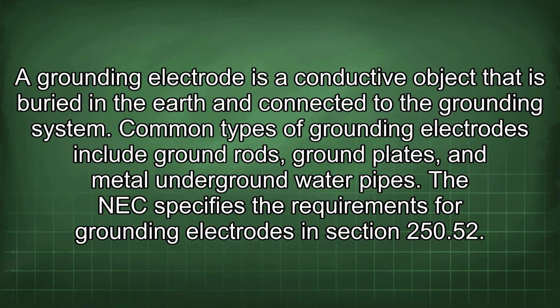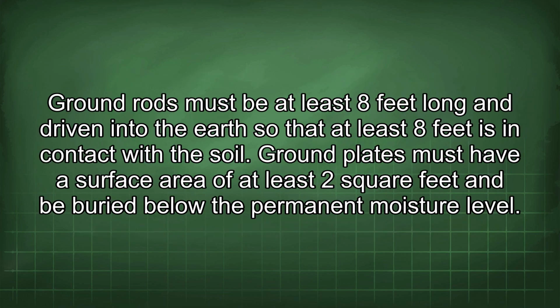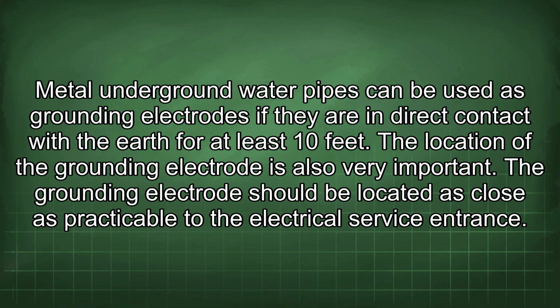A grounding electrode is a conductive object that is buried in the earth and connected to the grounding system. Common types of grounding electrodes include ground rods, ground plates, and metal underground water pipes. The NEC specifies the requirements for grounding electrodes in section 250.52. Ground rods must be at least 8 feet long and driven into the earth so that at least 8 feet is in contact with the soil. Ground plates must have a surface area of at least 2 square feet and be buried below the permanent moisture level. Metal underground water pipes can be used as grounding electrodes if they are in direct contact with the earth for at least 10 feet.